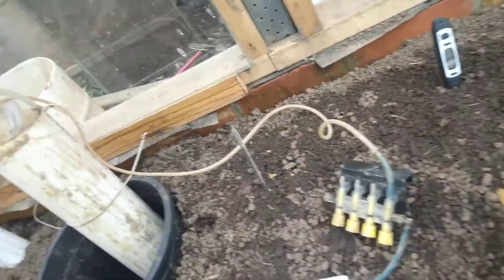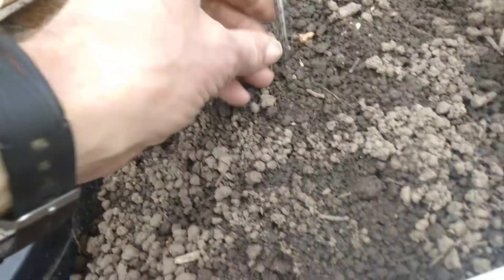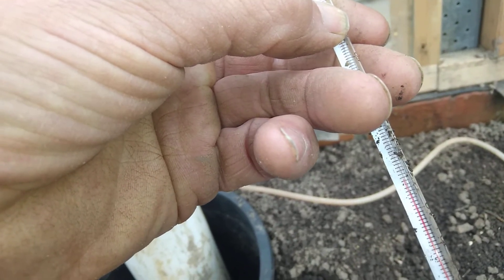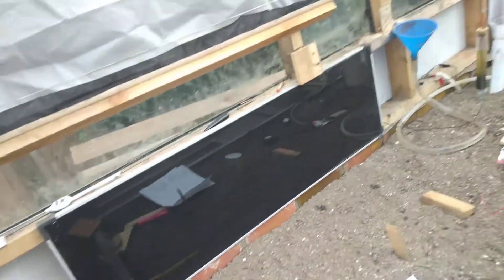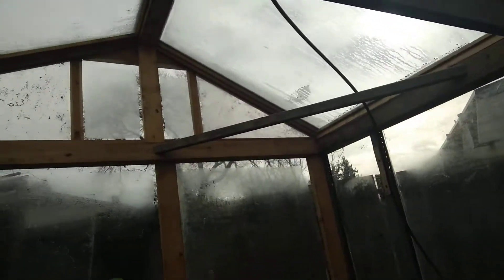This 8.4 reading is from a shallow sensor. I have another thermometer that goes deeper, down where the pipe is in the ground. At that depth it's about nine degrees — just over nine — so it's a little bit warmer deeper down in the soil. This is presumably because the air is warming it up over the course of the day. The system runs really fast when the sun shines, and then when the sun gets to the tree here, about halfway up, it pretty much shuts down.